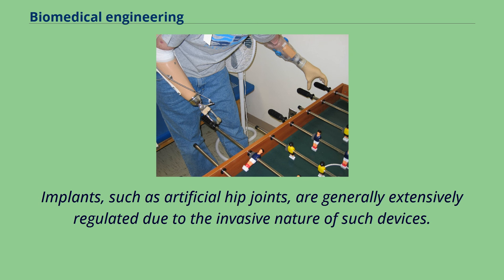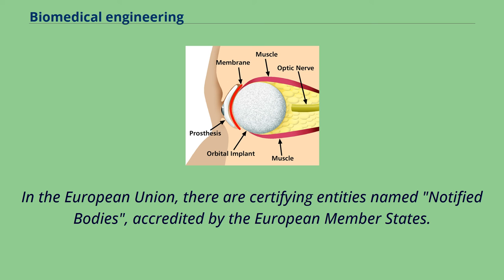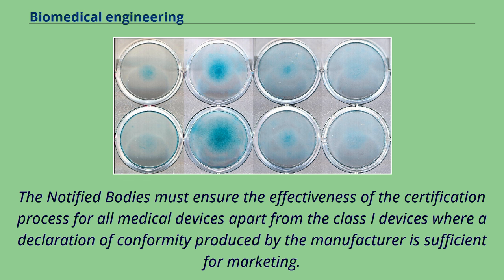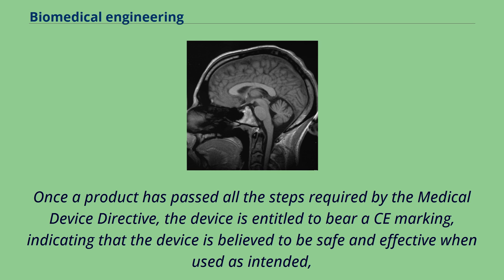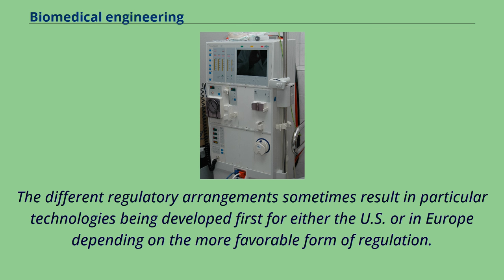Implants such as artificial hip joints are generally extensively regulated due to the invasive nature of such devices. In the European Union, there are certifying entities named notified bodies, accredited by the European member states, which must ensure the effectiveness of the certification process for all medical devices apart from class I devices. Once a product has passed all required steps, the device is entitled to bear a CE marking, indicating that the device is believed to be safe and effective when used as intended, and can be marketed within the European Union. Different regulatory arrangements sometimes result in particular technologies being developed first for either the US or Europe depending on the more favorable form of regulation.